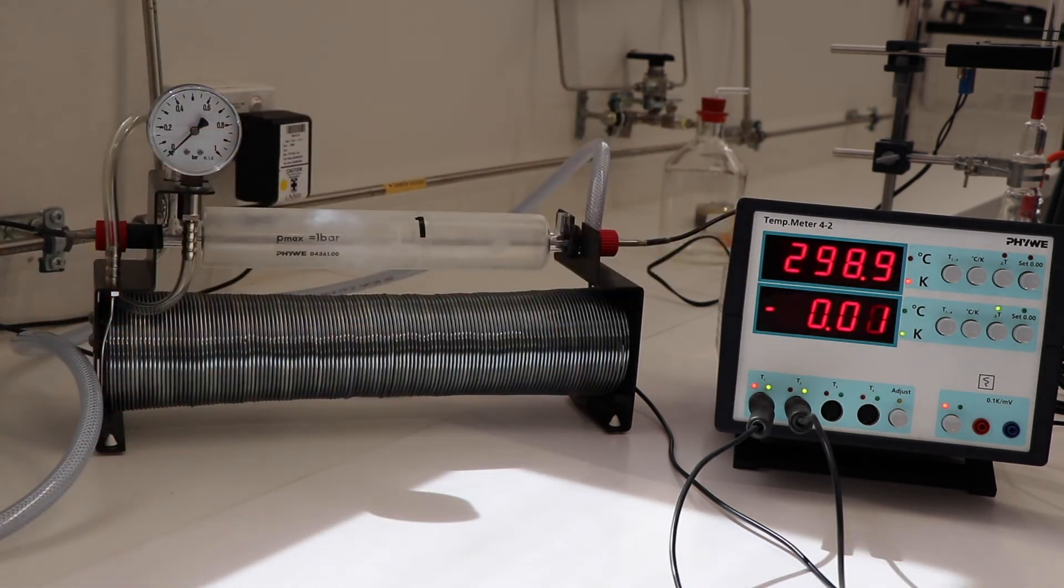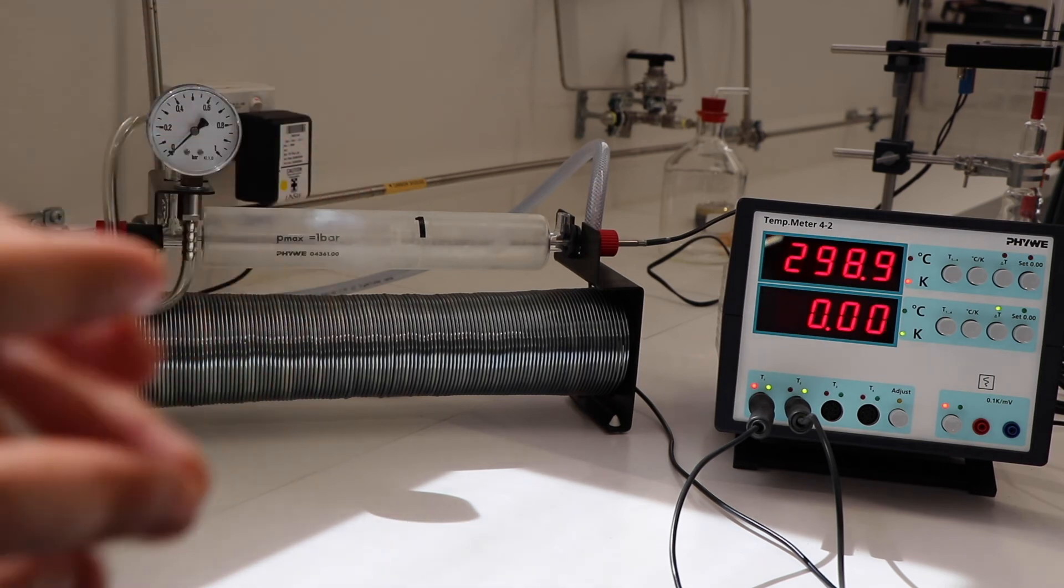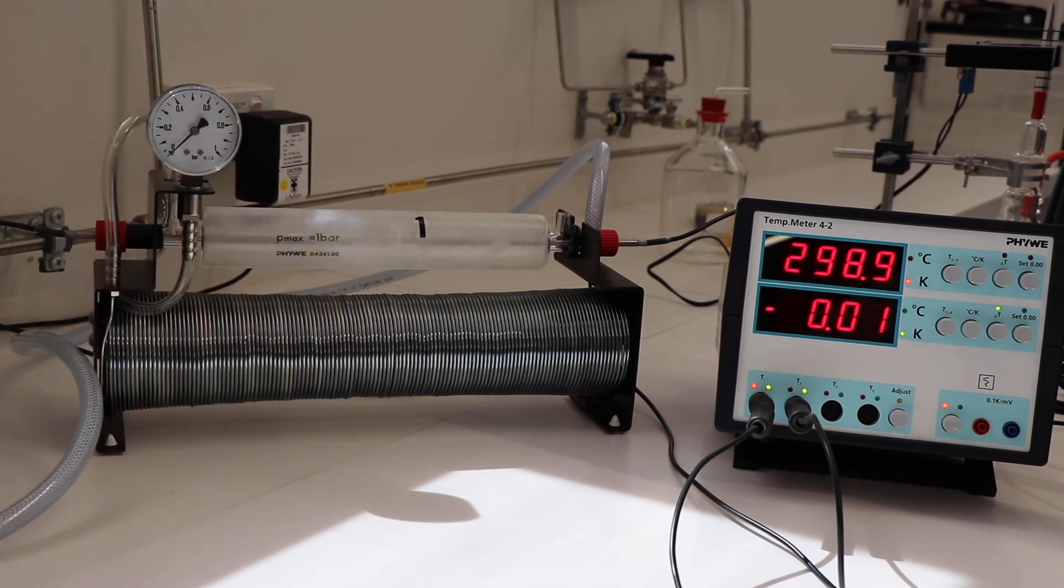For each bar value or pressure value, we need to wait 90 seconds to allow our system to go into thermal equilibrium before we can take a measurement of our change in temperature.